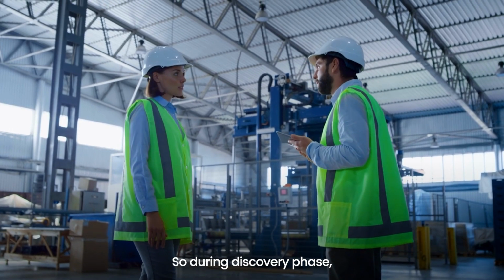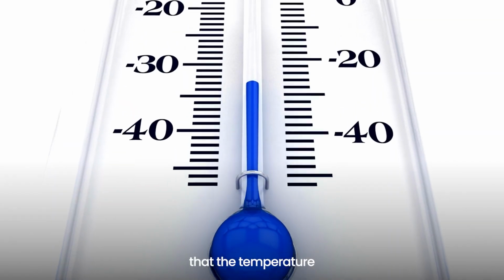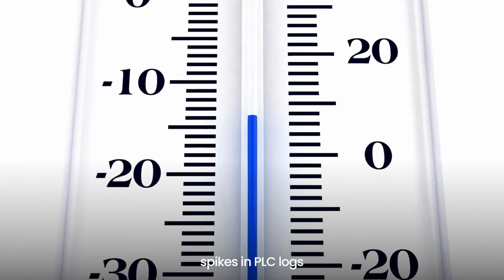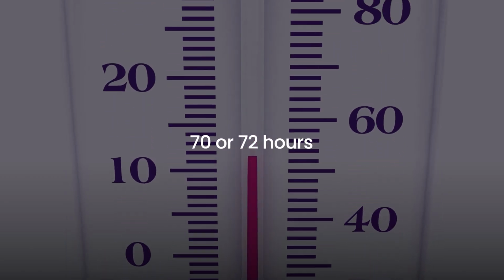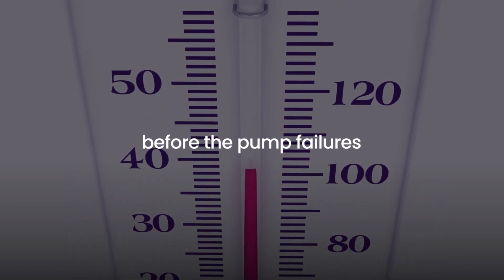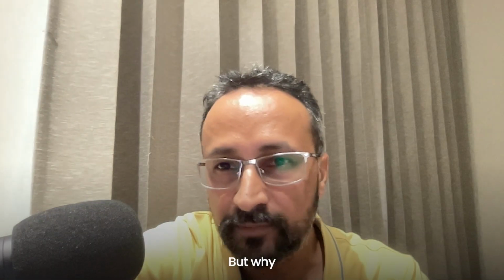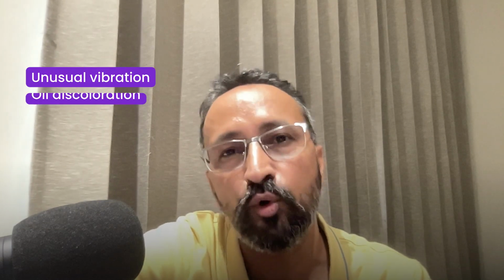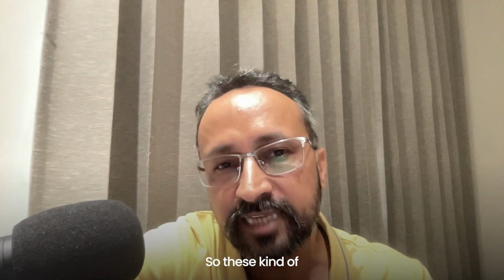During the discovery phase, we found that temperature spikes in PLC logs always occurred 70 to 72 hours before pump failures. But why? Cross-referencing maintenance logs, we saw notes like 'unusual vibration' and 'oil discoloration' - clues technicians were missing.